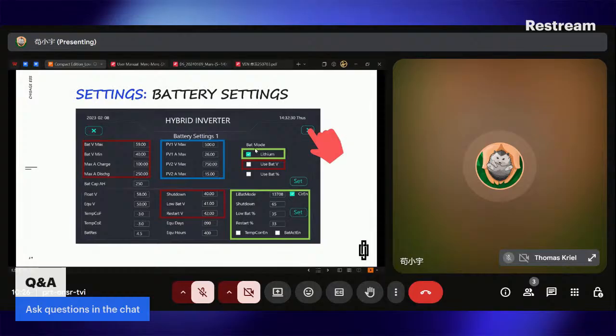And when you are using lithium mode, we'll need to check the settings in the green box, like the lithium battery mode. This part actually is reading from the BMS, so we don't need to change it. And for the shutdown SOC, low battery SOC, restart SOC, it's like when your SOC is lower than the low battery percentage, it will have an alarm, and you can check it on the inverter. And when the SOC drops lower than the shutdown SOC, if you have grid or PV power, it will stop output. If you only connect it to batteries, then the inverter will shut down. And when SOC is higher than the restart SOC, it will restart or recover the output.